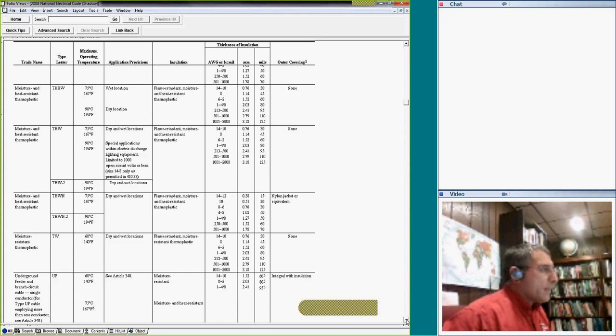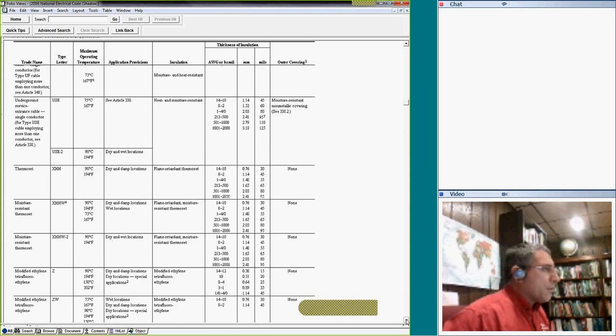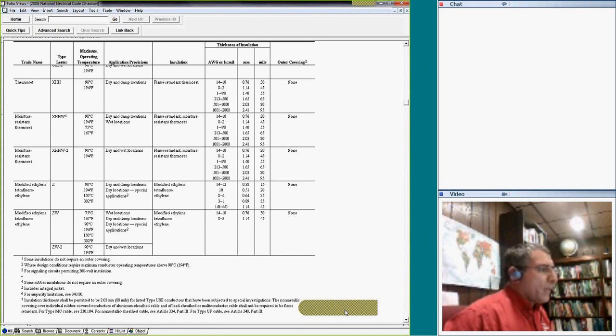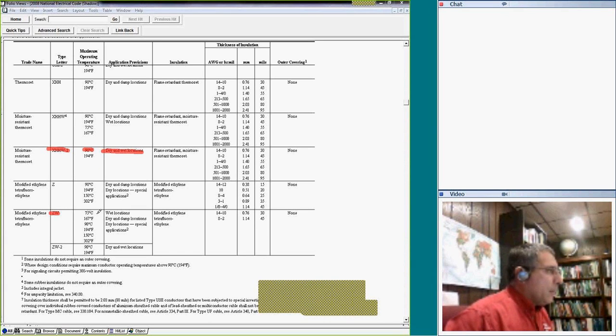What tells you what the insulation is rated for is the application. One interesting one is this baby here, XHHW-2. It's 90 degrees, dry or wet. Bring it on, no problem. If you have a ZW, 75 in a wet location, you can have 90 degrees for dry with special permission. So you can see, guys, if you use ZW-2, 90 degrees, dry and wet location, no problem.